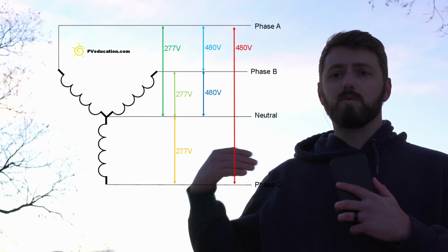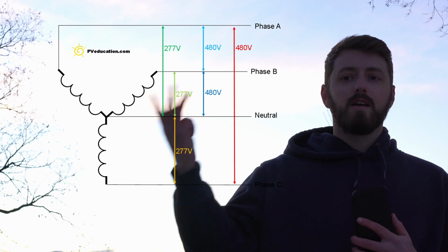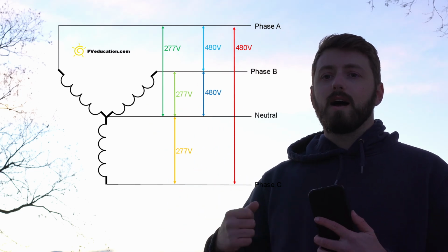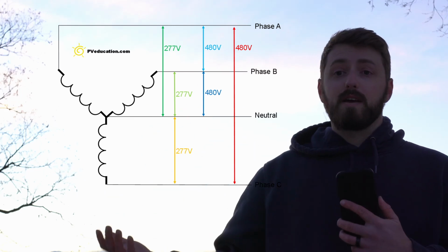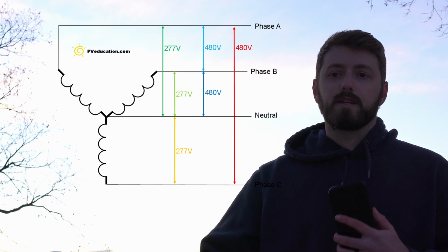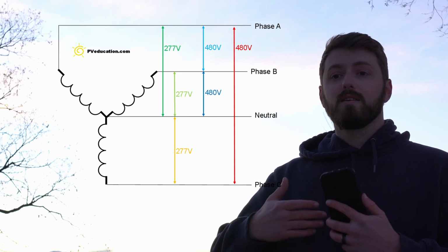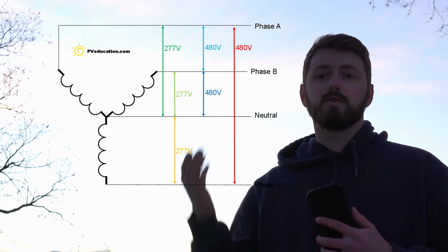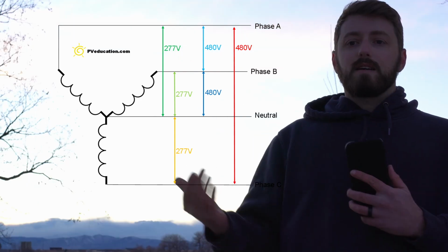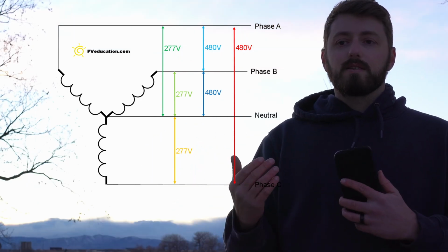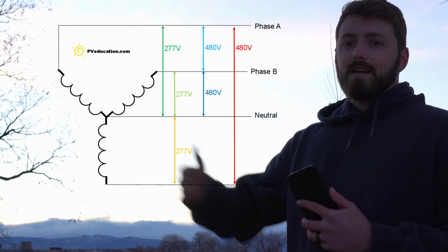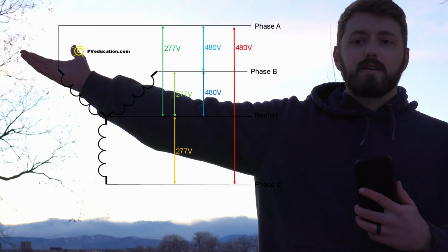What I do want to talk about specifically is phase to neutral or phase to ground voltage versus a phase to phase voltage measurement. We often use Y-connected systems where we have 3 phases and a neutral wire that we can have either 3-phase loads like motors and transformers connected to, or we can connect individual single-phase loads between the phase and the neutral. If I take a voltage measurement from one hot phase to ground or to neutral, in the example here, I'll have 277 volts.